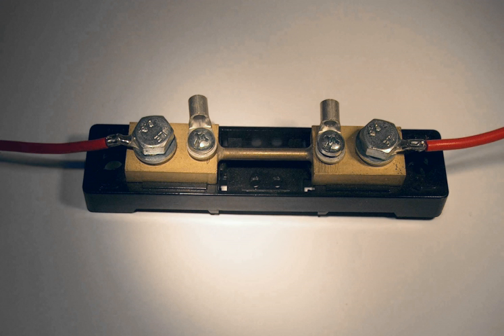A shunt in the grounded conductor may not detect leakage current that bypasses the shunt, but it will not experience high common mode voltage to ground. The load is removed from a direct path to ground, which may create problems for control circuitry, result in unwanted emissions, or both.